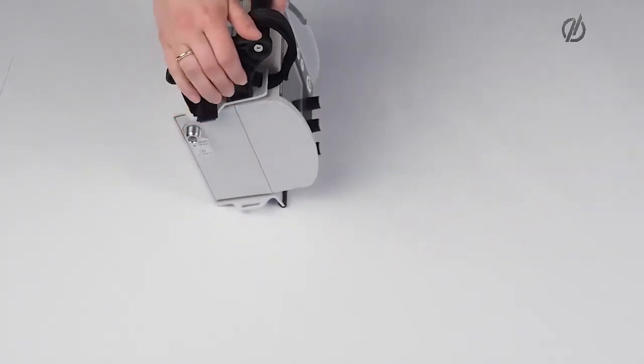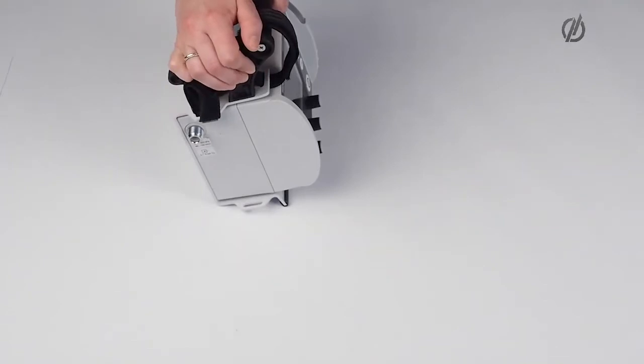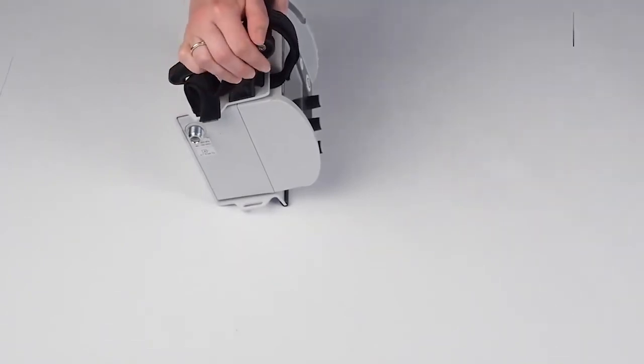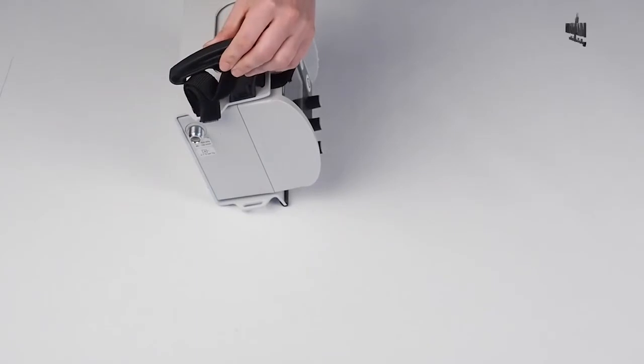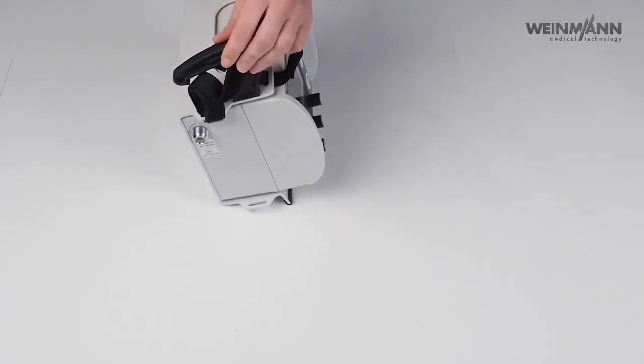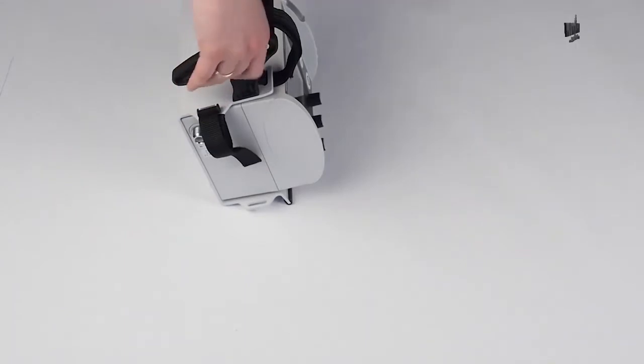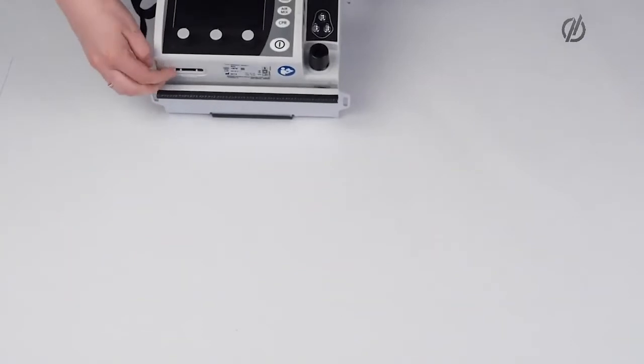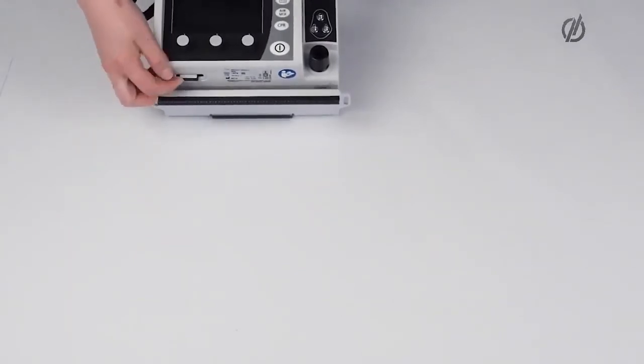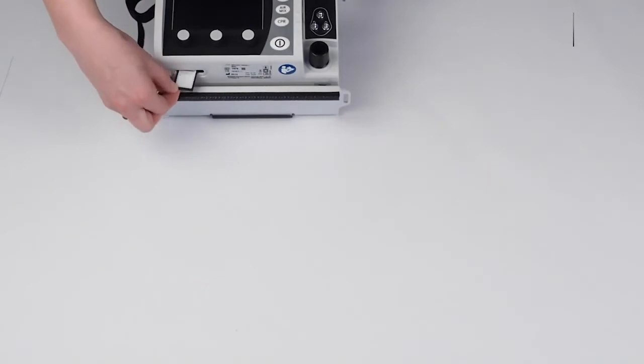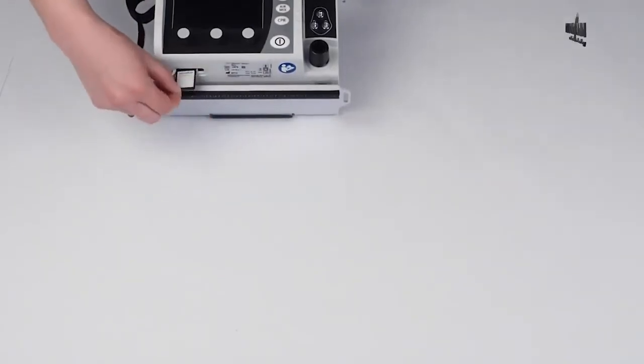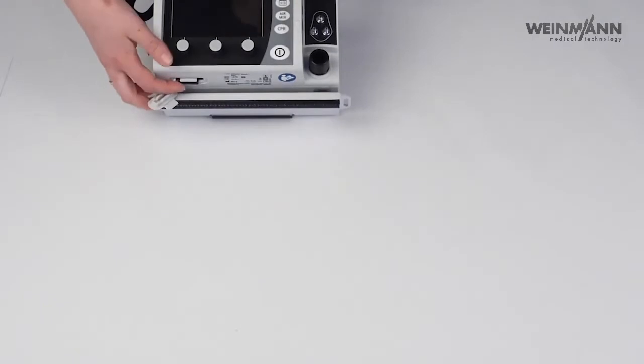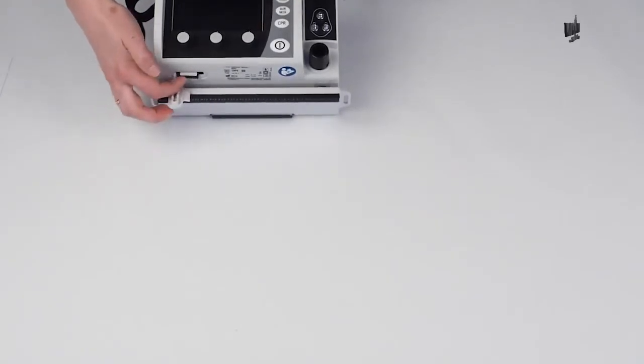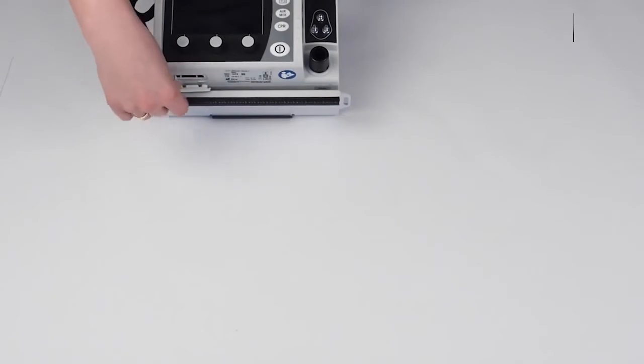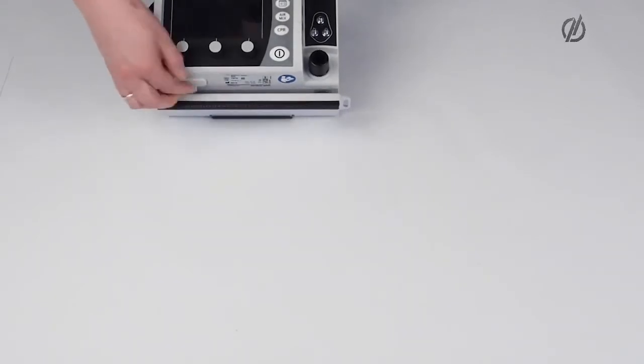On the right-hand side, we have our connection for the gas supply. So this is the pneumatically driven device, so please make sure always to connect the oxygen before starting up the device. Also, on the bottom of the device, we have a slot for an SD card, which you can take out by just clicking on the SD card. And on this card, settings and also ventilation data are stored, and you can read it out via this SD card slot.